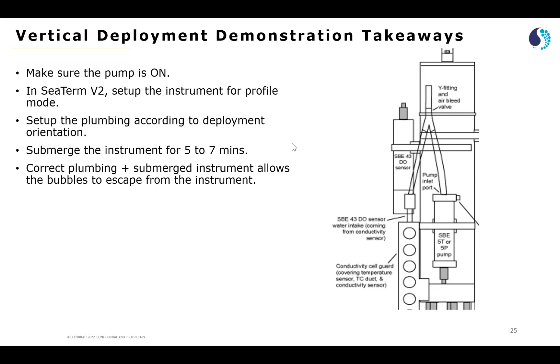Submerge the instrument in the water for 5 to 7 minutes until all the bubbles come out. So basically, correct plumbing as per the orientation you want to deploy the instrument in, and submerging the instrument for 5 to 7 or 10 minutes as per where you are deploying it, and allowing the bubbles to escape will get you high quality data.